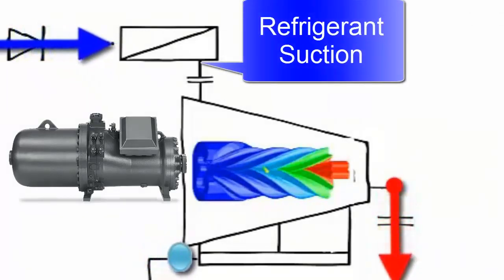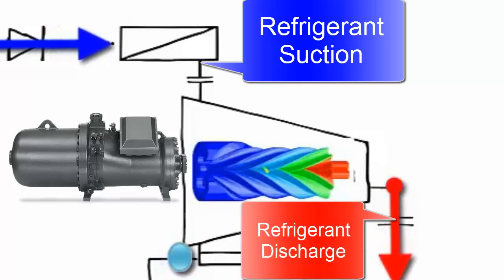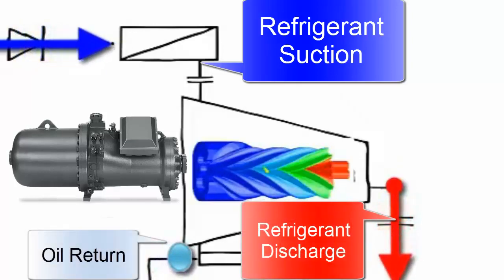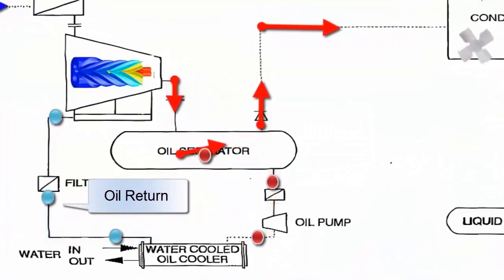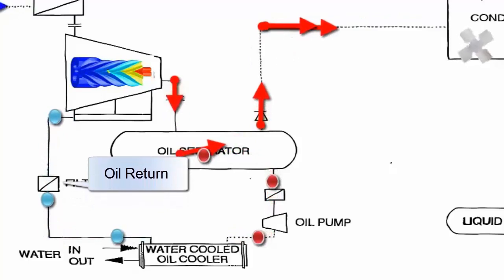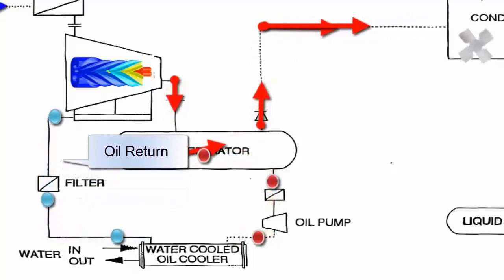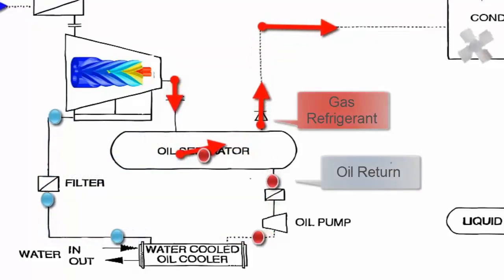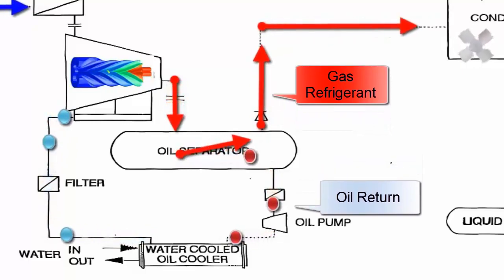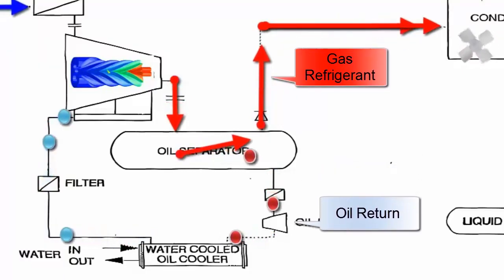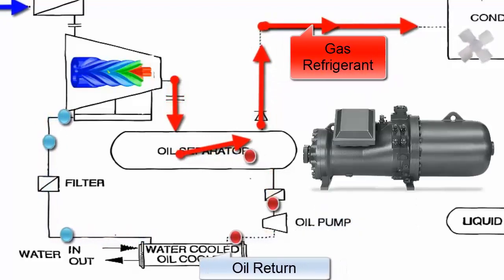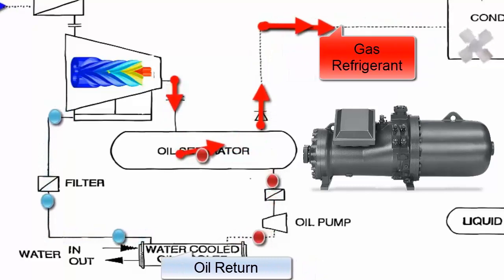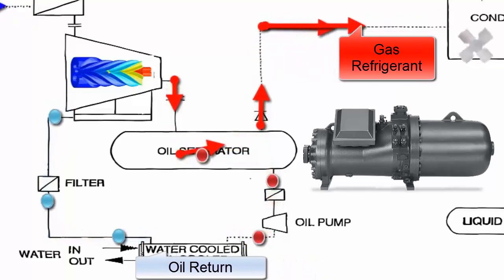Screw compressors are the most commonly used compressors for industrial refrigeration, in medium and high refrigeration capacity applications, due to their high efficiency. Screw compressors with oil injection have an almost isothermal compression process, as the heat generated by the compression process leaves the refrigerant and is absorbed by the oil. Given that oil is undesirable in other parts of the refrigeration system, oil flooded screw compressors bring with them the need for a strategy for proper lubricant management.